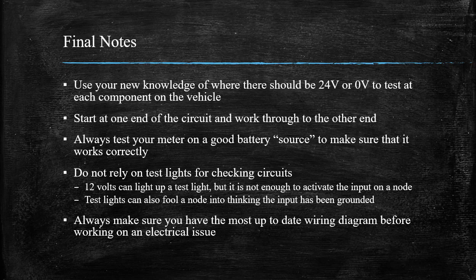There may be things happening after it goes into one of those modules that require more advanced troubleshooting skills. However, most of the time the problem is just a poor connection to the node. If you have good power going into the nodes and it's still not functioning correctly, you may just have a faulty node. In that case, you can swap one node with another that doesn't use that input or output, and that will tell you if the node is good or not.